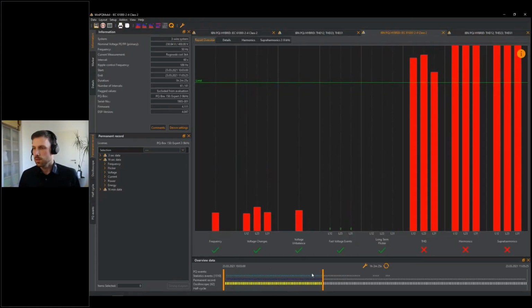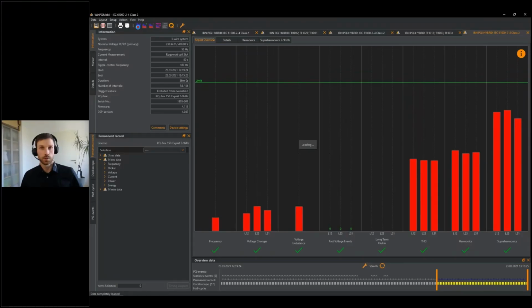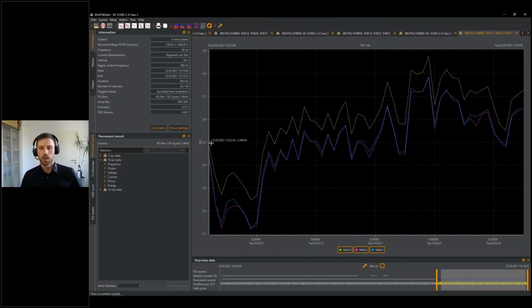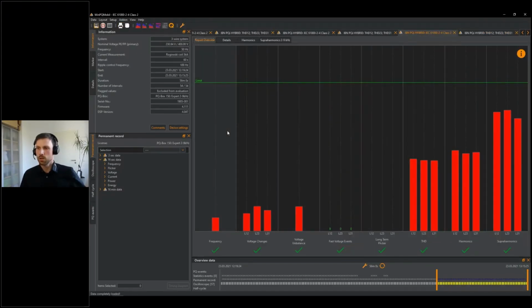Everything looks bad. Well, at the beginning, now I change the evaluation period and shift it to the right side, to the end of the measurement, and click on refresh. And now I see only this data is evaluated. I click on norm evaluation again, and now it looks different. Everything looks good. So if I click on here, now the THD dropped to 3%, for example. And now I can compare all the values. I can export this to a PDF and say, well, old versus new, for example. So this is very, very easy.